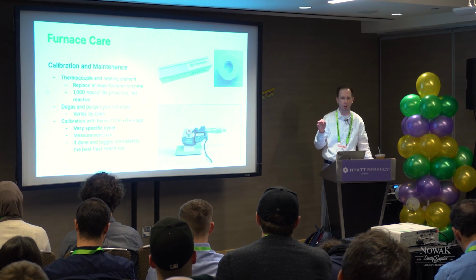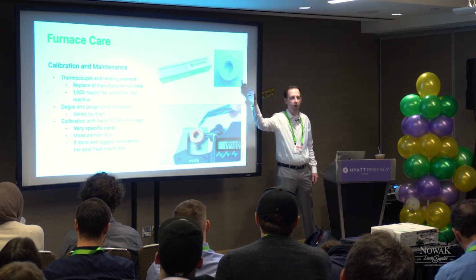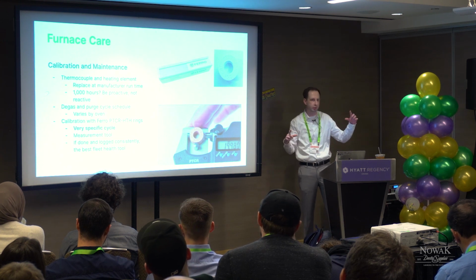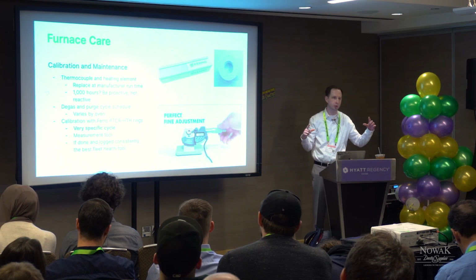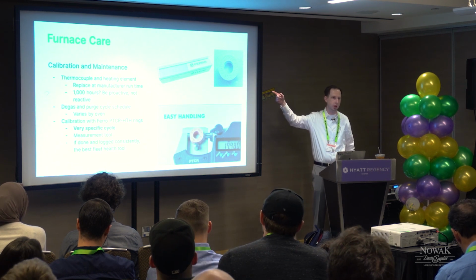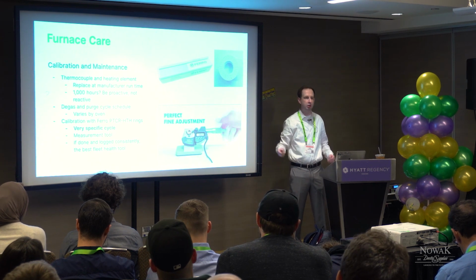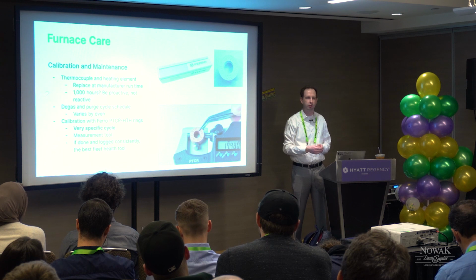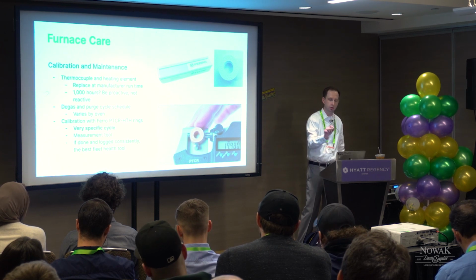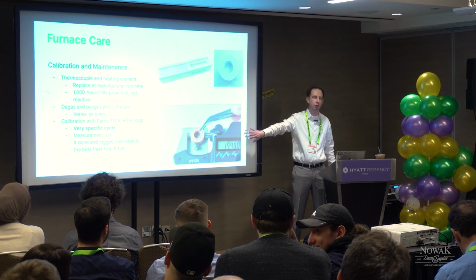They also have, by batch, if you notice this number right up there, 451, each Ferro ring can come from a different manufacturing batch, and they all have their different conversion table associated with it. So you go buy 2 of these boxes, and they could be from different batches. They have a different table you have to refer to. So when you read out your measurement, that could mean you're at 1500C, or 1550 or whatever.